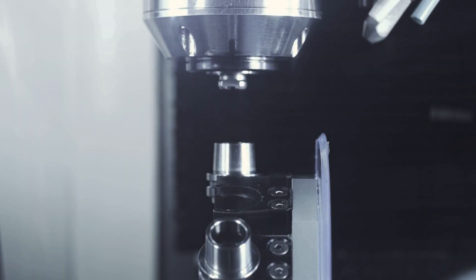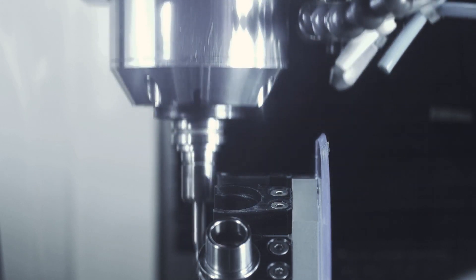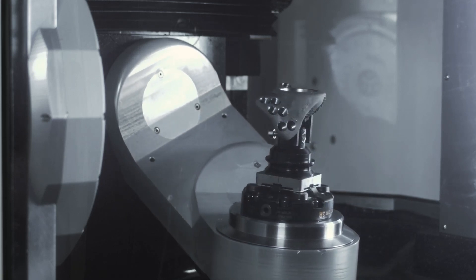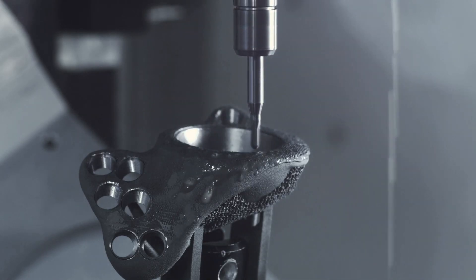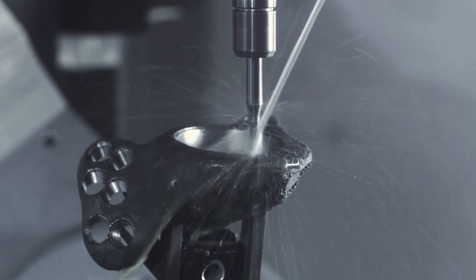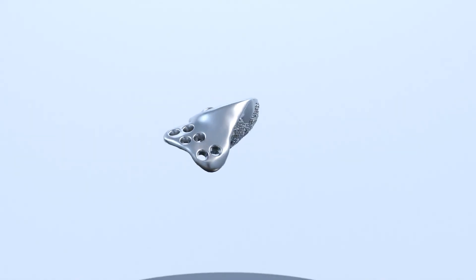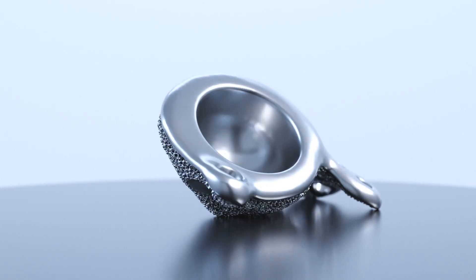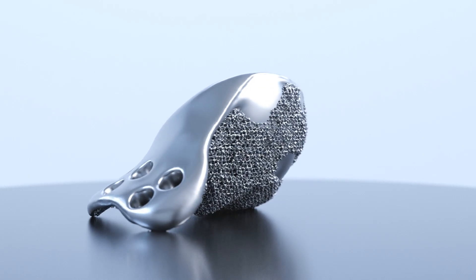As implants are 3D printed, the finishing process is performed — first to remove internal metal tensions generated during the 3D metal printing process, then support structures are removed. Depending on the technology used, there is a surface finishing process involving mechanical treatment using sandblasting, milling, vibrating hopper, ultrasonic cleaning, high pressure water jet and polishing. To increase the implant-bone contact surface and improve osteointegration, polished implants are additionally sanded, anodized, or coated with different hybrid coatings.